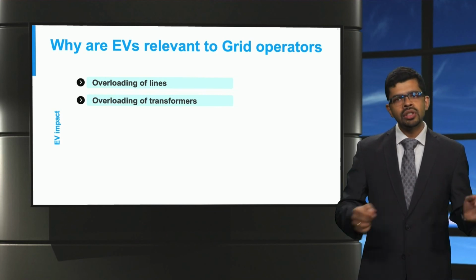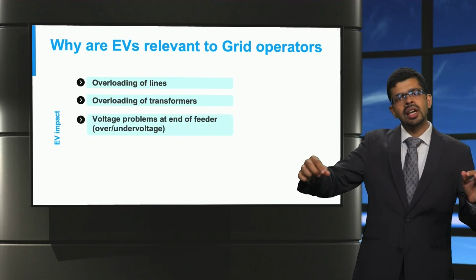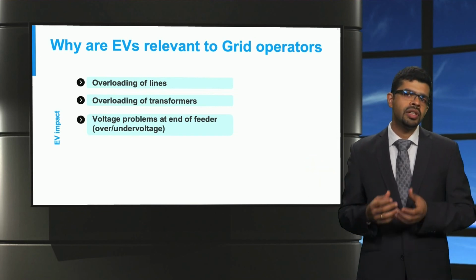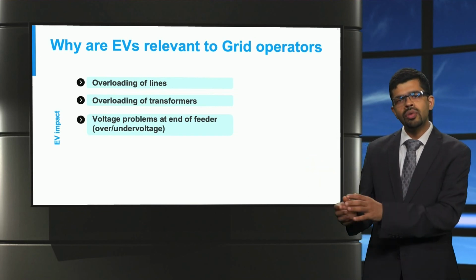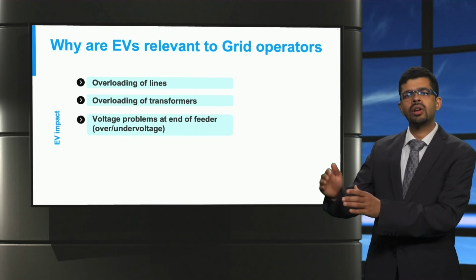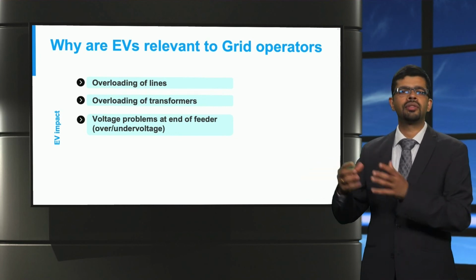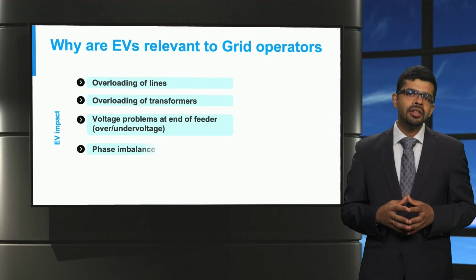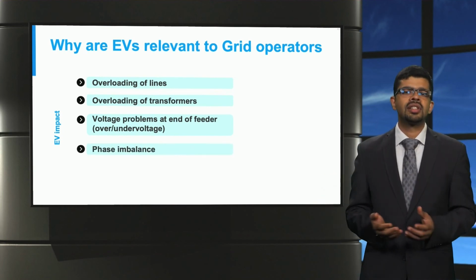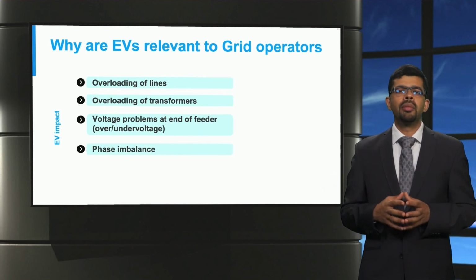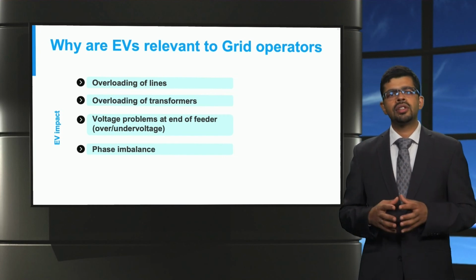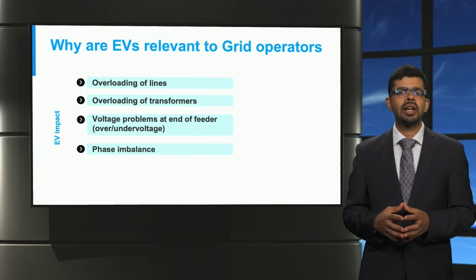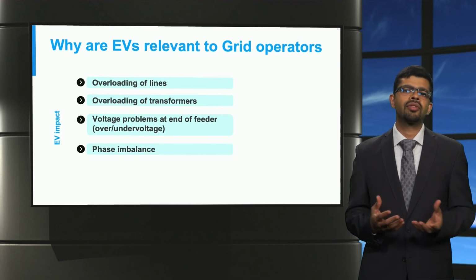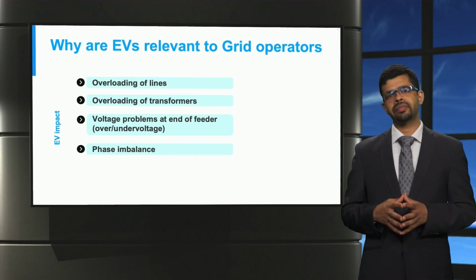In networks with long feeder cables, the demand of electric vehicles coupled with distributed generation can cause overvoltage or undervoltage to specific customers located at the end of the feeders. Furthermore, in three-phase networks, imbalanced EV charging because of loads on one or two phases will cause phase imbalances that might be a challenge to rectify from the grid operator side.